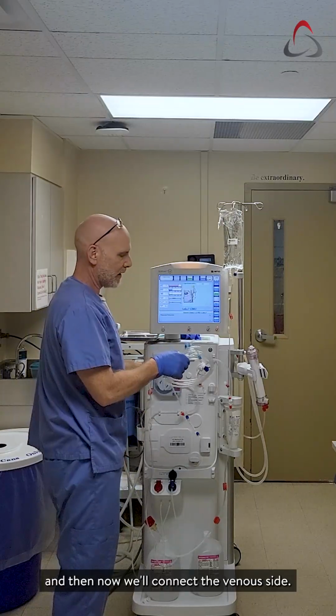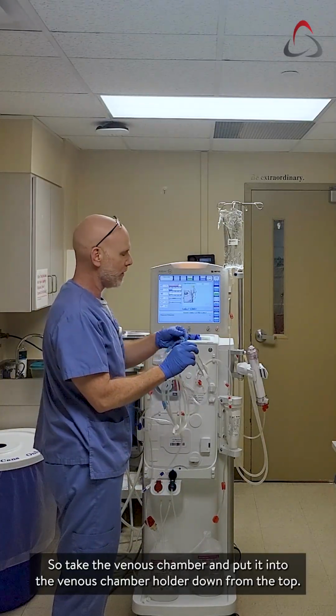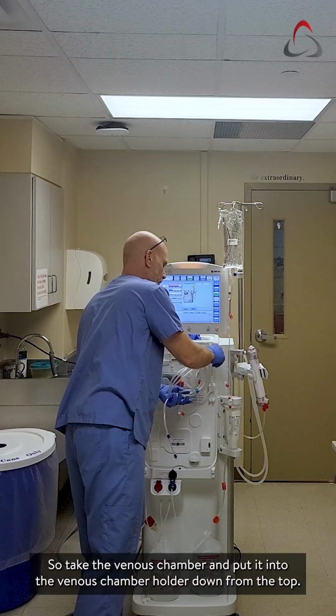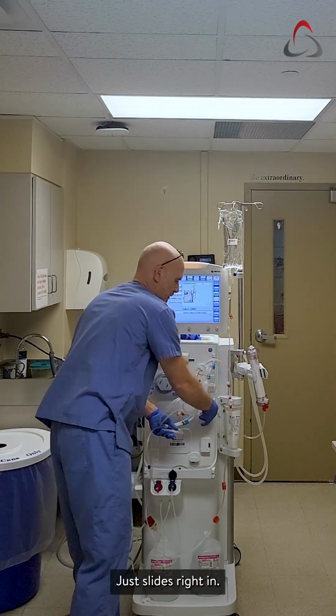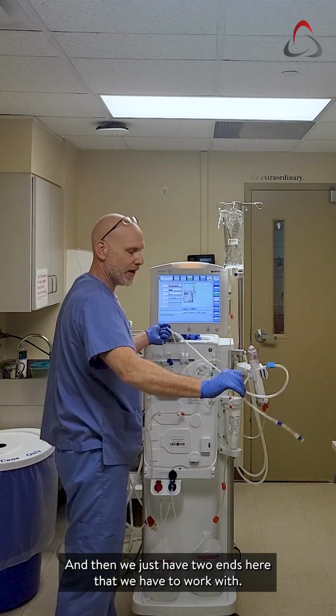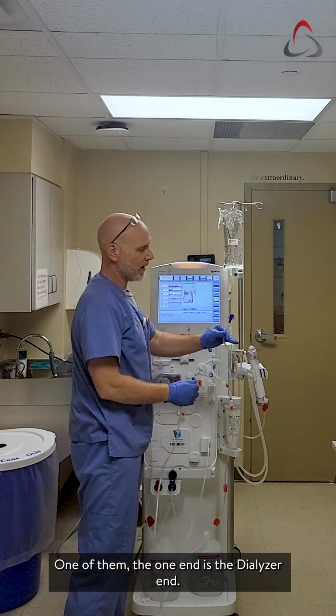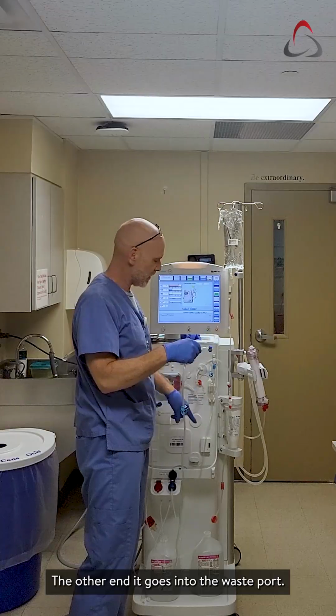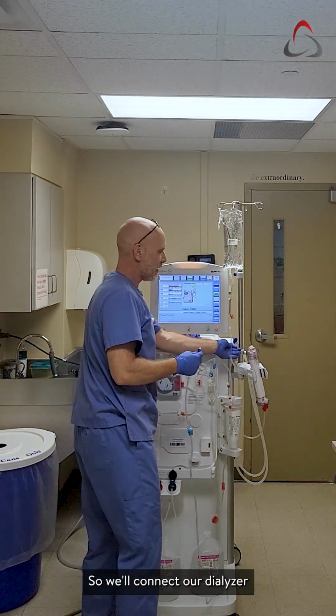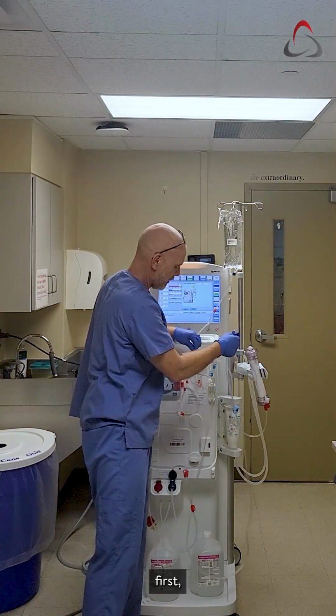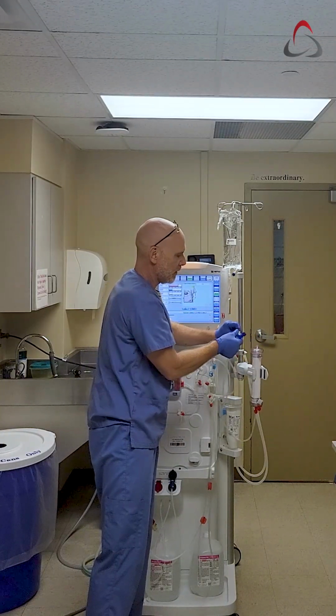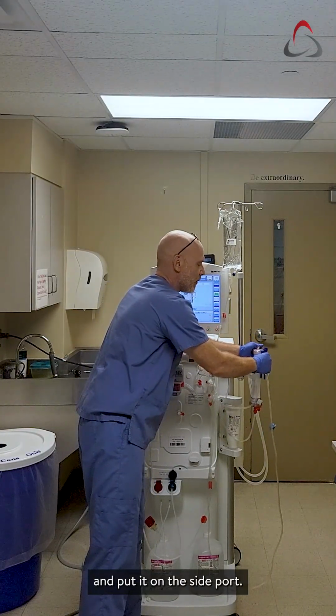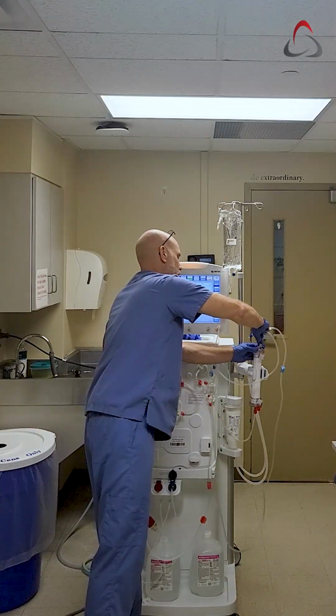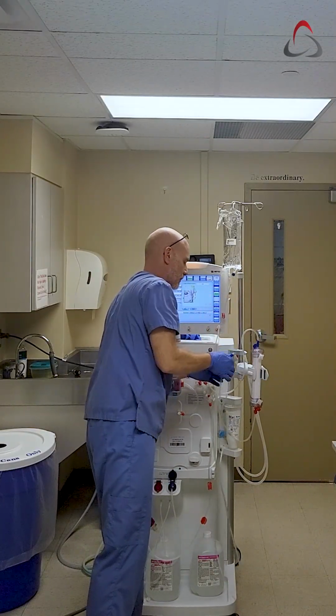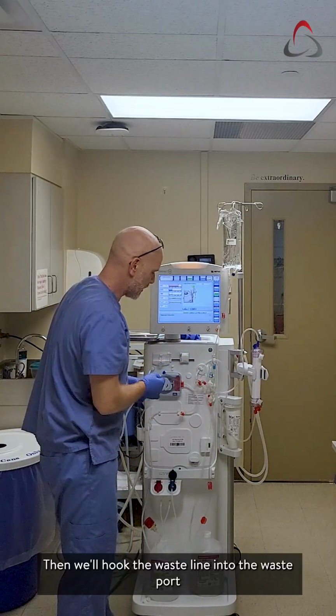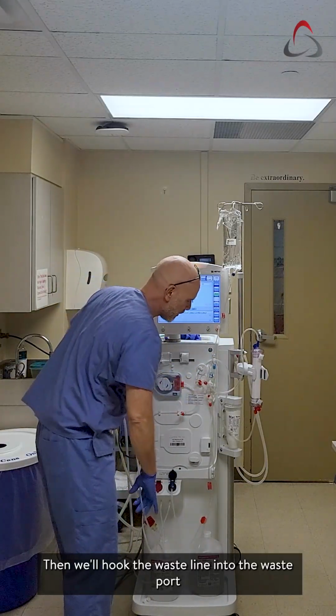And then now we'll connect the venous side. So take the venous chamber and put it into the venous chamber holder down from the top, just slides right in. And then we just have two ends here that we have to work with. One end is the dialyzer end. The other end goes into the waste port. So we'll connect our dialyzer first. Take the cap off the dialyzer and put it on the side port. And then we'll put the waste line into the waste port.